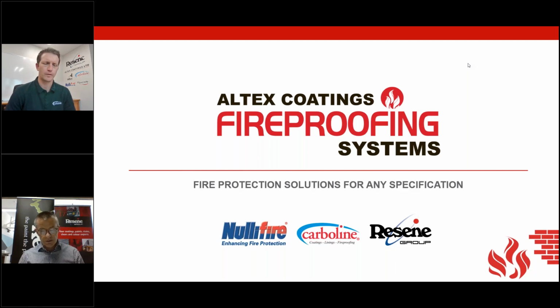Another very good question, and you touched on this earlier in your presentations, I think. Are there efficiency gains in splitting up a project into the various types of intumescent or cementitious materials? Absolutely there is, definitely. We know of several very smart contractors that have approached it this way when quoting for jobs. They'll split a project up into different environmental categories with regards to the location of the fire-rated steelwork. So, for example, anything exterior exposed will go for our SC902 product, which is the most suitable for that type of exterior environment. Anything within the perimeter zone is going to get hit by water and rain constantly during the construction phase. Again, you'd be using the more durable products, SC902, or even the Pyrocrete 40, being the cementitious type of material.